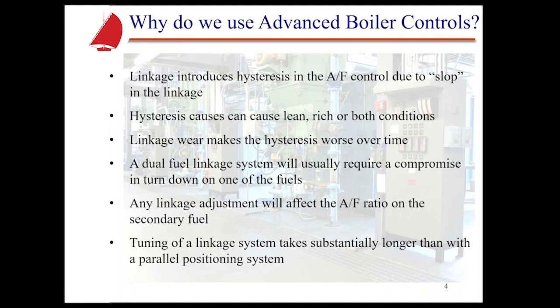And any linkage adjustment that we end up making on gas or on oil, we have to go to the secondary fuel or the other fuel to verify and see how it has affected that particular fuel ratio. So this is a very complicated and usually time-consuming method to actually be able to get both fuels in the proper area for combustion across the firing rate range. So it's going to take longer to actually tune that system properly. And if it's not done, then the secondary fuel is not going to actually combust properly, and you may be in a very rich or very lean condition. So it is more time consuming.